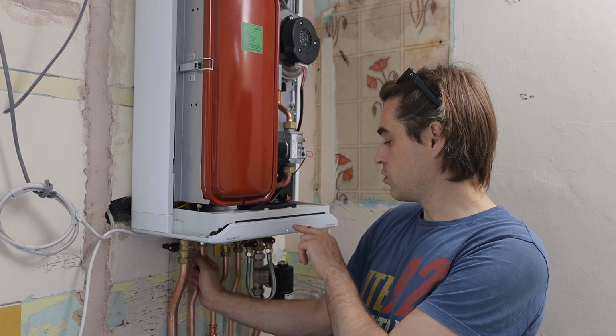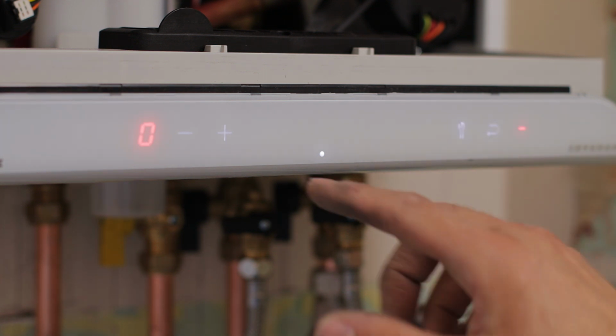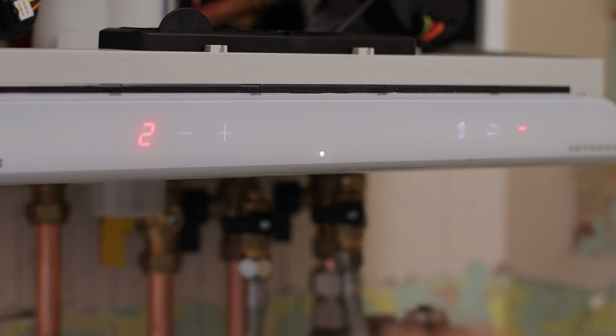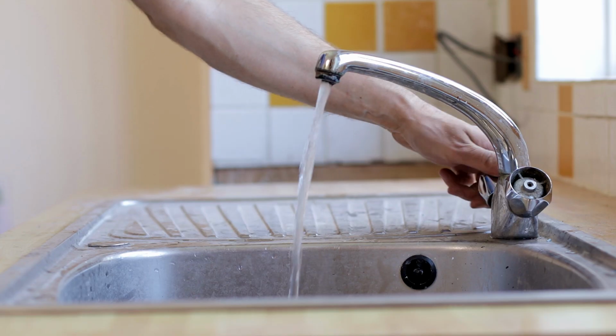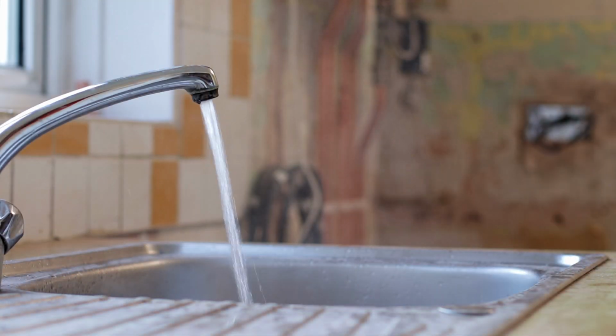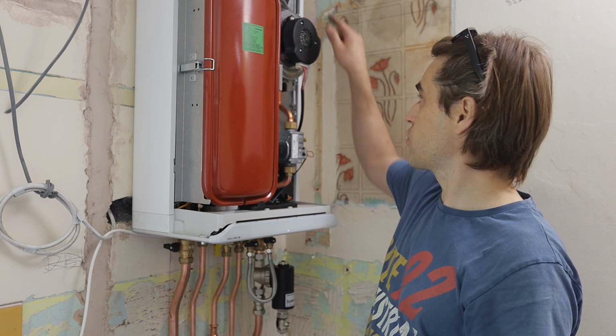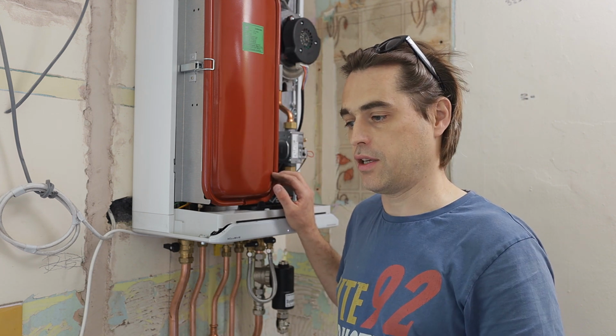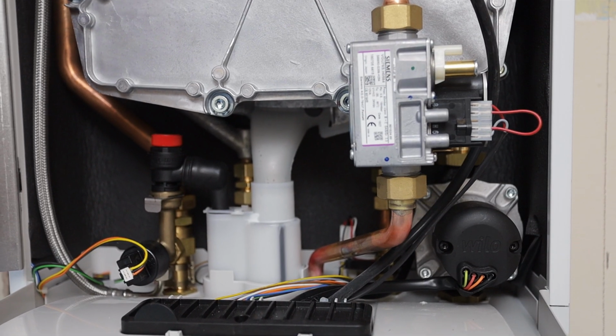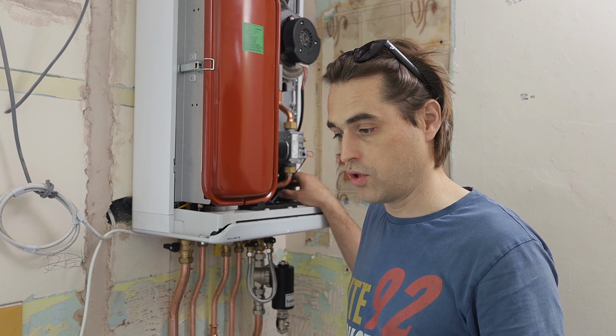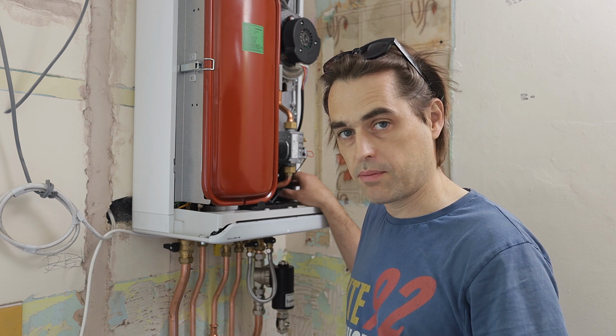All you have to do is go to the menu, go to the service mode, and change the parameters of the boiler from combi boiler to multi-point water heater, and you can use hot water. So my hot water is on right now, because the way this boiler operates, the heat exchanger heats the water directly on domestic hot water function. So when you turn the hot water on, the cold water goes through the main heat exchanger and is heated directly by gas, and the pump doesn't start in hot water mode, so we don't need central heating connected, and you don't need the system to be pressurized, because you're not exchanging water to water through the plate heat exchanger.